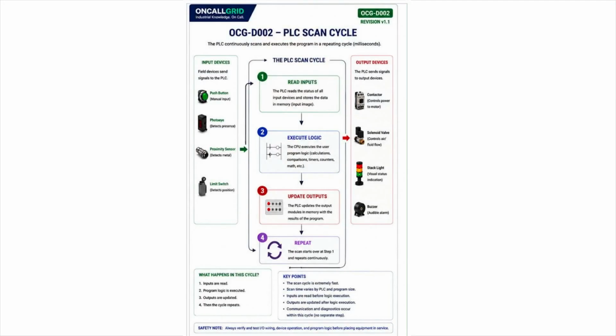Now here's the part that trips people up when they're new. How does the PLC actually think? It runs in a loop called the scan cycle, and it happens over and over continuously in milliseconds. Step 1, read inputs. The PLC checks every input device and stores that status in memory. Step 2, execute logic. The CPU runs your program against that input data: comparisons, timers, counters, math, whatever your logic calls for. Step 3, update outputs. Based on what the logic decided, the PLC turns outputs on or off. Step 4, repeat. It just starts over at step 1 continuously. That's it. One thing worth knowing, communication and diagnostics aren't some separate fifth step. They're happening inside this same cycle in the background.